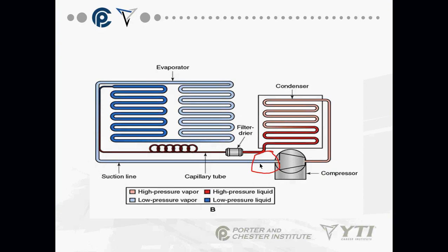So a lot of times what technicians do is they'll put their suction line filter dryer here. It has a replaceable core. So they'll come back probably 2 weeks later and replace that core with a new core, and they'll leave it. Does it have a shut-off valve? Yeah, and if it doesn't, you make very sure it does when you install these things. You will use a little bit of refrigerant opening that up to replace the core.